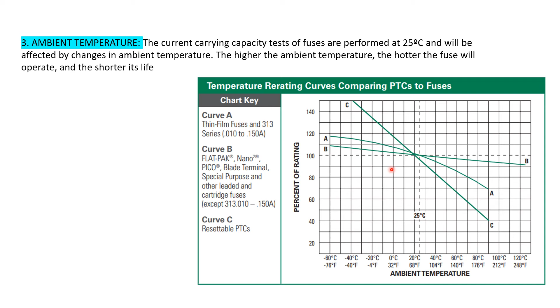So let's consider if you are using a PTC and you are operating somewhere around 80 degrees centigrade, you have to derate almost 60% of your rating. So if you wanted to use 1 ampere of current, you must take a 1.6 ampere current rating of the fuse. So this is a very important parameter, where your fuse is going to be used. This curve will give you the guide of how much derating factor you can keep, and if you're using PTC, it means the derating factor should be very high. You must make it a very clear statement during your design selection.